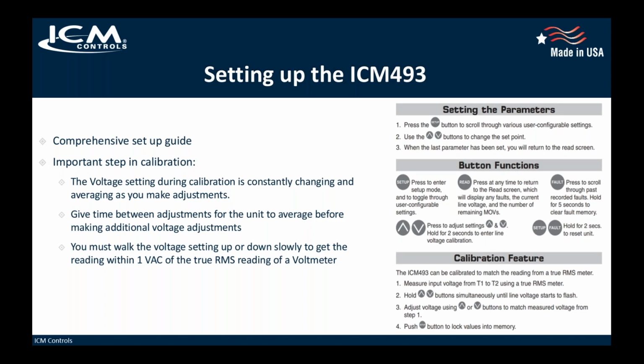So in the calibration mode, you'll raise the voltage a little bit or lower it, depending on where you need to be, and then it'll average. Then you have to do it again, and you just walk it down. It only takes a couple of minutes, and you can get it within about a volt of the true RMS reading. But it's important to know that you can't just ride it right up, because if you try to ride it right up to the point where you want it to be, it'll average, and then it'll be over, and you'll be fighting yourself. But if you just make small increments to the top or where you want to be, then it'll be right on spot.